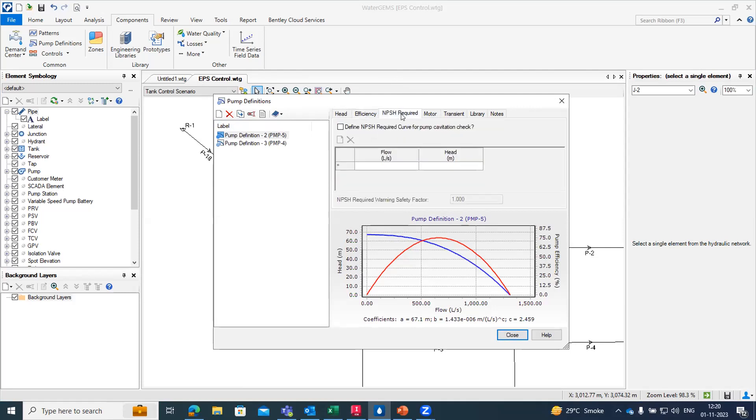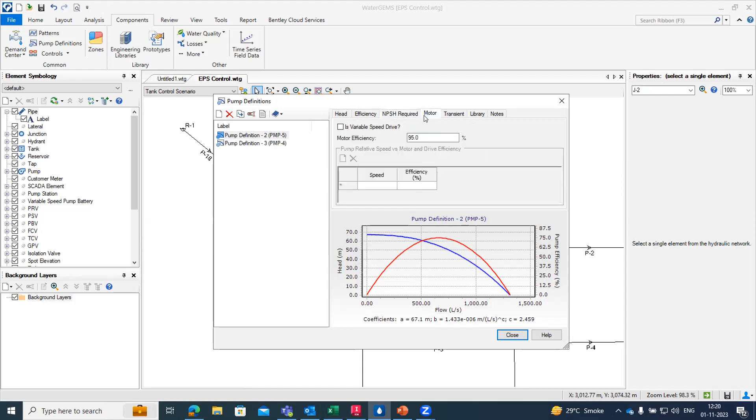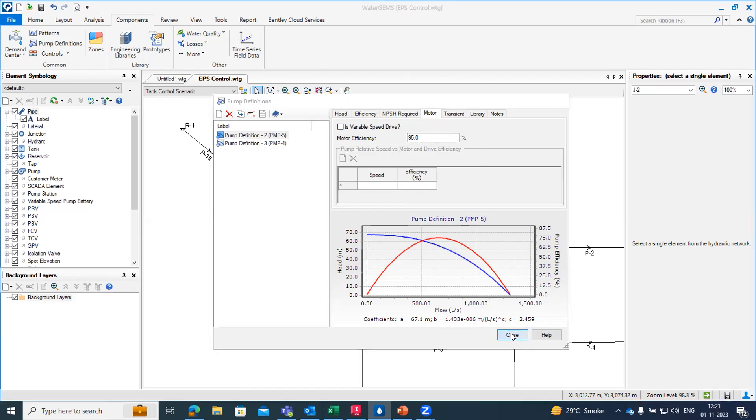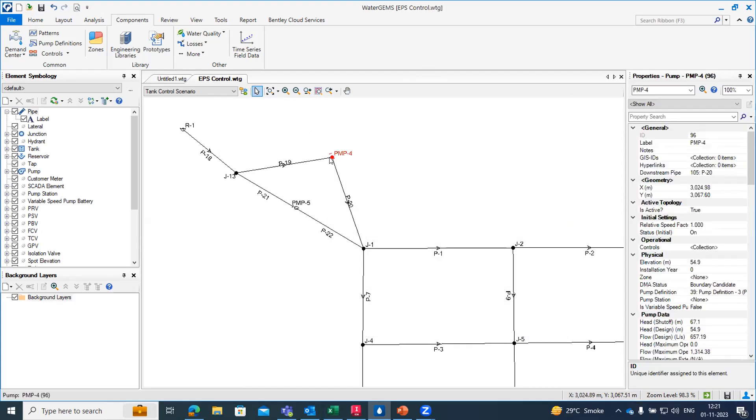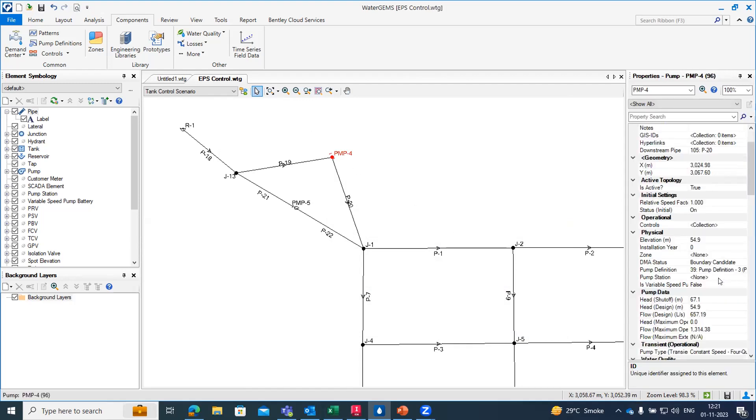NPSH which is net positive suction head, if it is required we can do that also. And for the motor, how much efficiency is for the motor we can give that also. Once we create the pump definition, we simply have to open the property for the pump and from there we have to assign it, the pump definition that we have just created from definition.